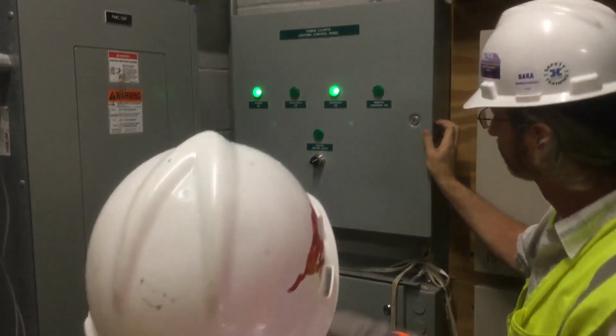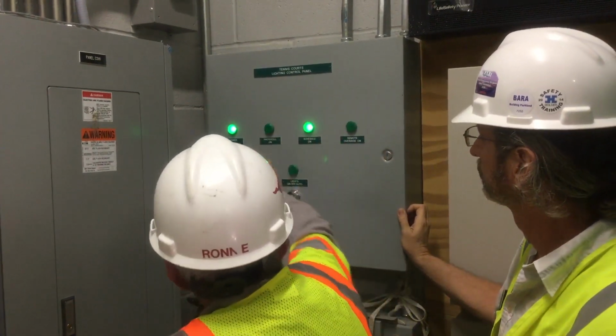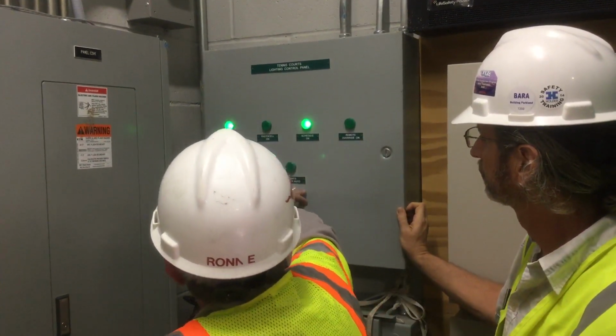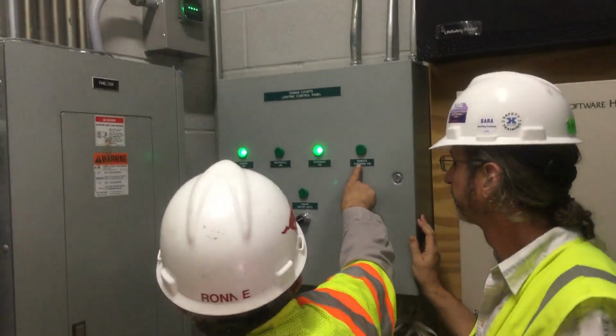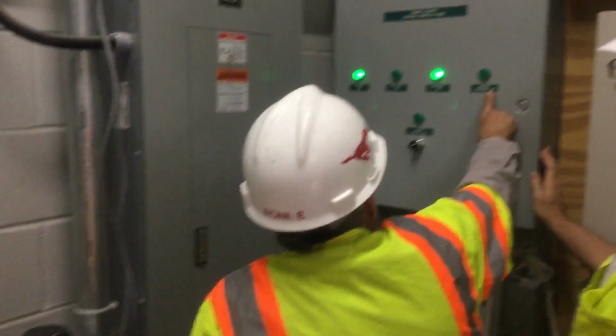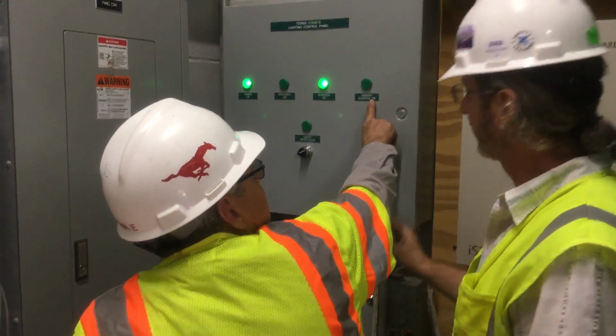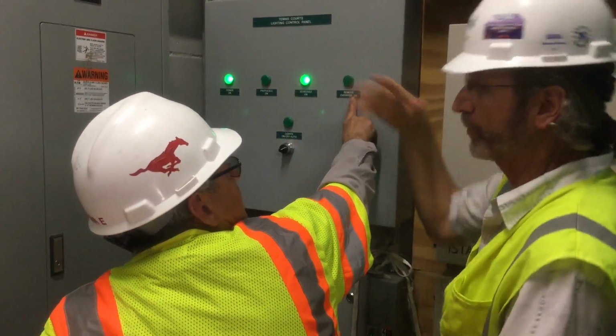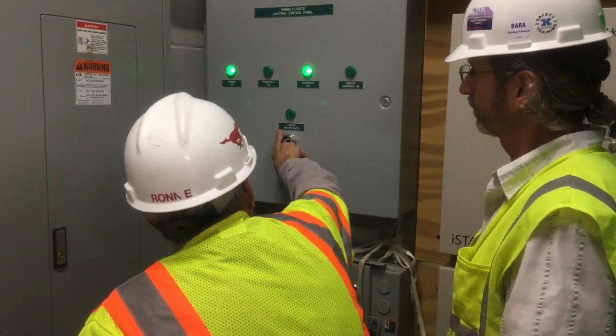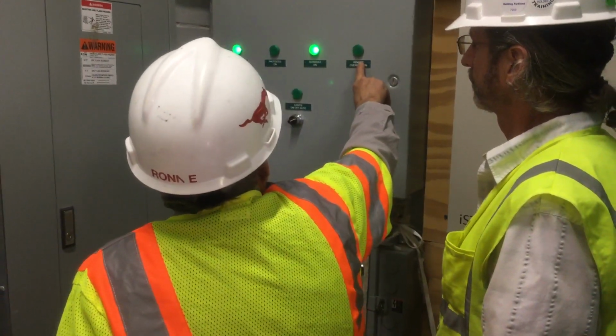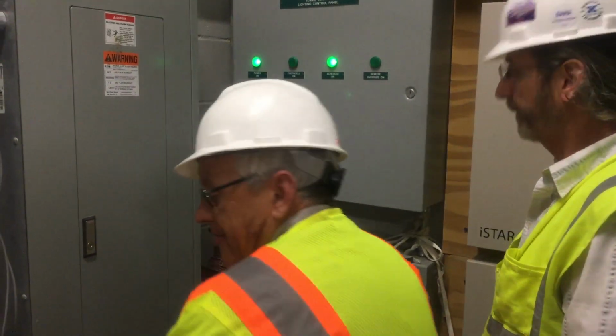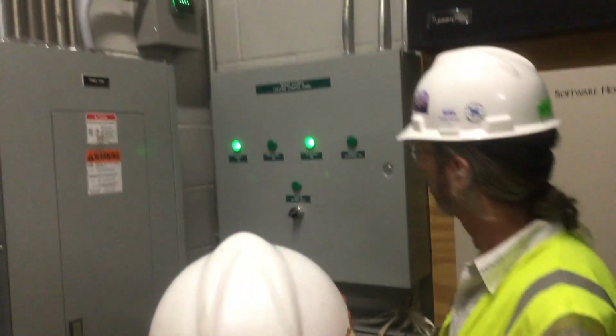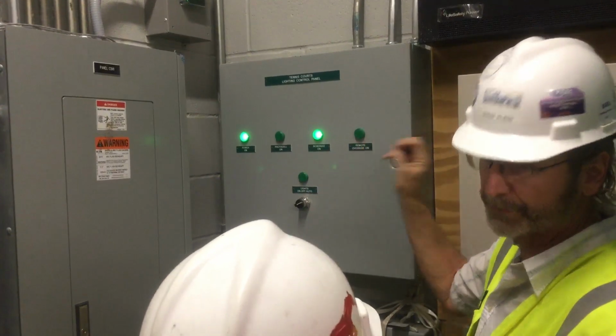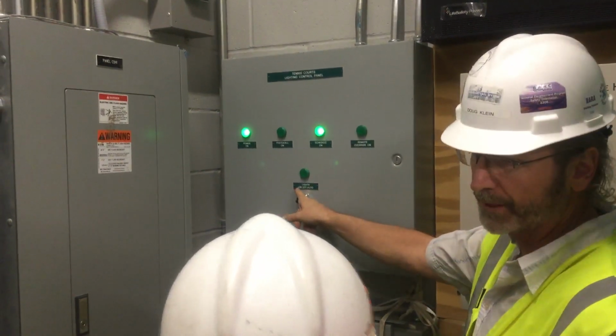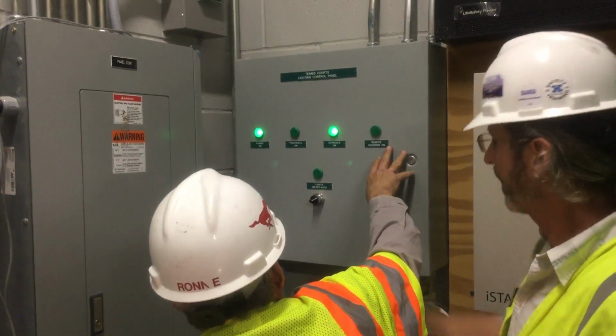I was just curious about something—if you turn this to on because you want the lights on, does that override things? They can't come in through the controls and say 'oh, the lights are on, we'll turn them off'? That's a good point—if either one of these is overridden, it's overridden. So if we turned this to on, the plant or whoever cannot go into the computer and override what we just did. Correct, that's exactly right, good point—they'll try that every time. This needs to be in off or auto for that to work. Well, actually it still works, it just piles on top. And vice versa, if they have it on remote, then it's on no matter what—we can't just turn this off and turn their system off. Correct. Gotcha—correct, it's the same on both sides.